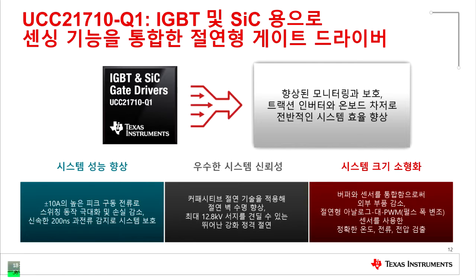Another point is strong system reliability, specifically the insulation barrier. I talked about the trend toward 400 volt, 800 volt and even higher, which means this is a very critical, life-critical voltage. So the isolation technology used is of major importance. TI has its industry-leading reinforced isolation built into this part, meaning you can use it up to a DC bus voltage of 1.5 kilovolts, a typical isolation voltage of 5.7 kilovolts, and surge immunity up to 12.8 kilovolts.